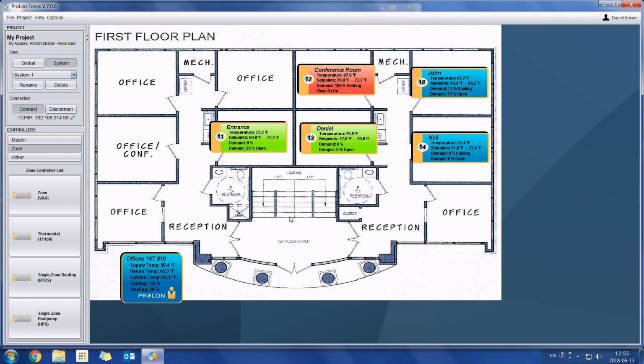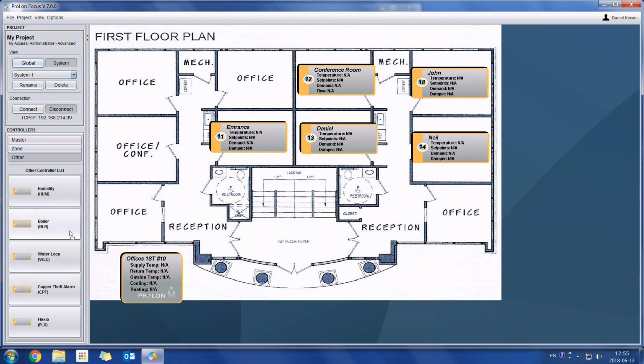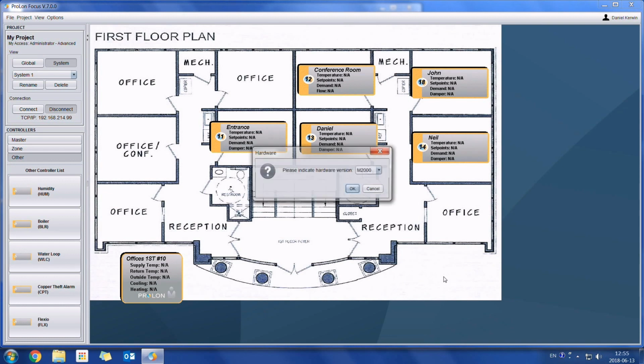Okay. The next controller I want to show is our boiler controller. We do not have one currently on the system which I am on right now, so I'm just going to disconnect. All of the icons are going to go gray, and now I'm simply going to bring in an offline boiler. So I'll just go here and drag and drop my boiler controller, and I'll give it address 50.